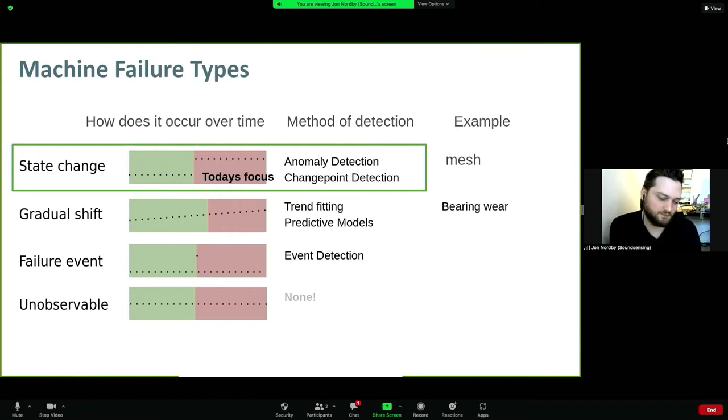We focus mostly on the top here, which we call a state change, where you have a relatively abrupt failure. This could actually happen at the end of a gradual shift. For example, if you have a bearing that's been operating okay for many years, towards the end lubrication might have gone out and it deteriorates faster. This is a threshold, the state change that we can detect. The techniques used are anomaly detection and change point detection.